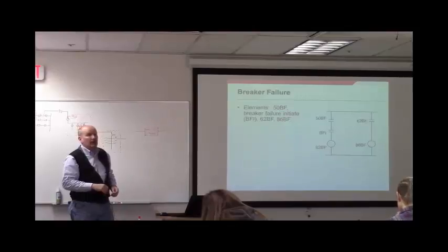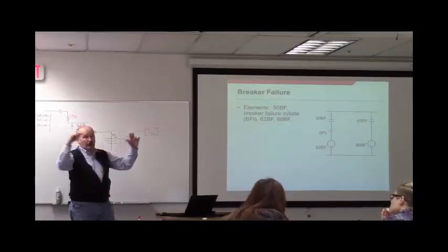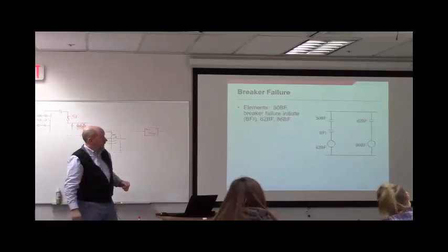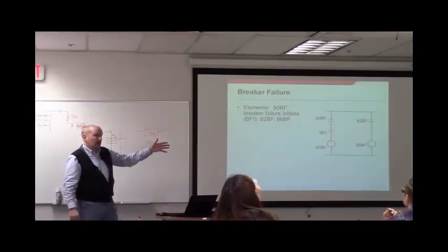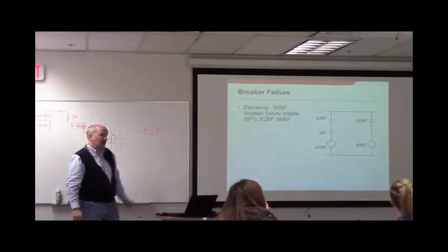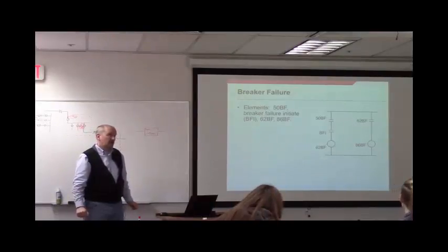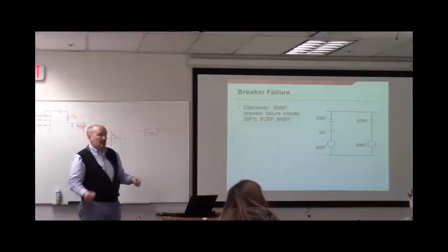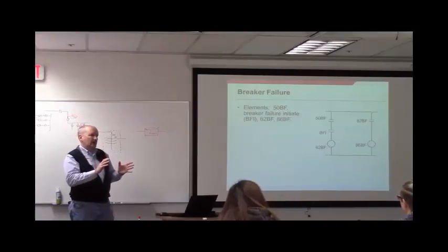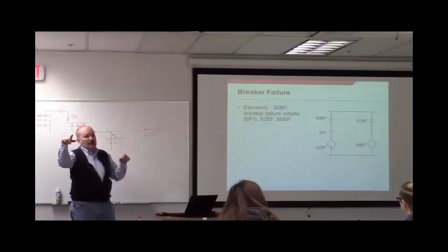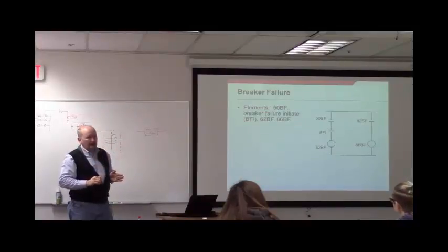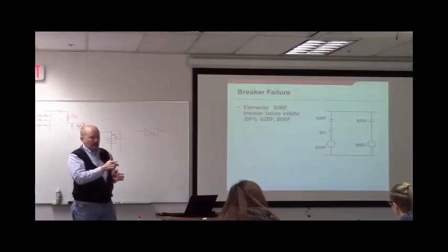If the timer times out, you close that contact and trip a lockout relay — that's when you clean house and trip all adjacent breakers. Implicit in this is that the 50BF will drop out at the exact instant fault current stops going through the breaker. It's not going to pick up and stay on a few more cycles — it comes up and drops right back out as soon as the fault is cleared.